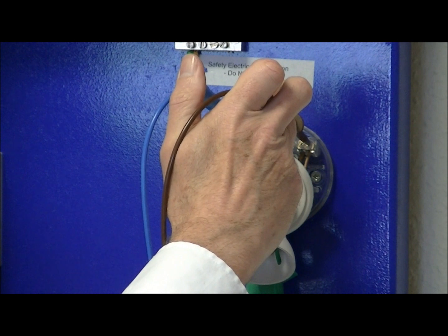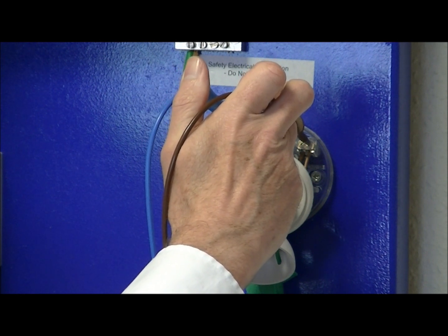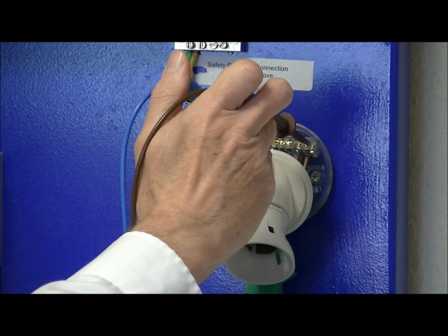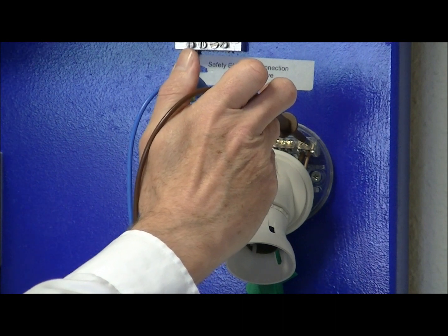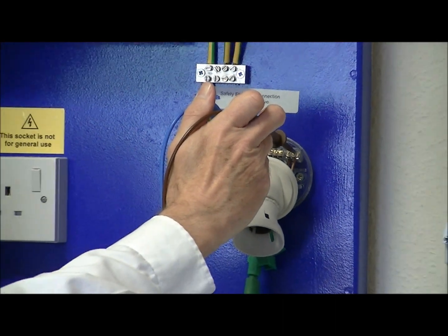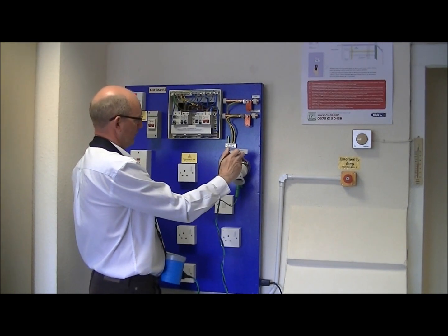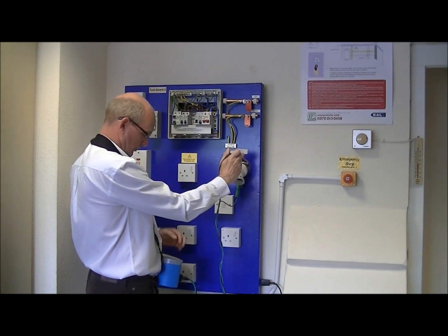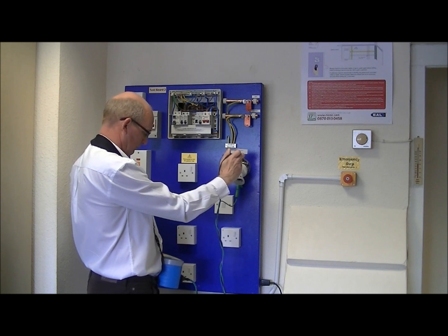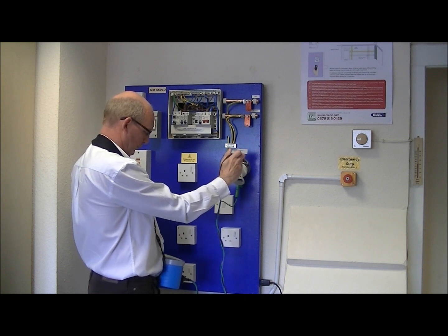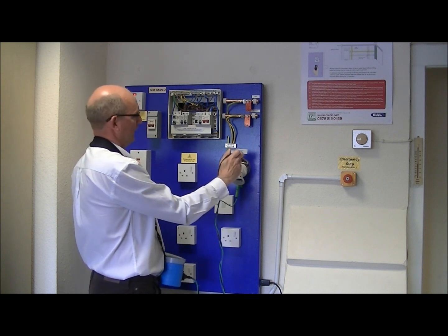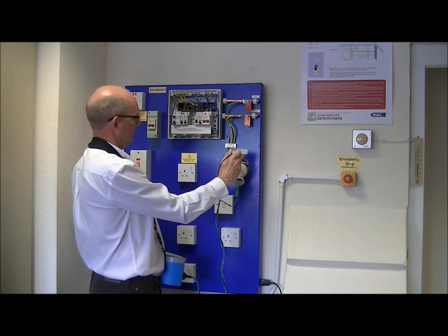We then need to energise the circuit via the circuit breaker and make sure the lights on the switch are on. So my meter is telling me we've got a live supply at this point now. So at the furthest point of the circuit, we've got earth fault loop impedance tester selected. I'm ready to test. So it's now running the test, and we have a figure of 0.88 ohms. So that is the ZS for this lighting circuit.